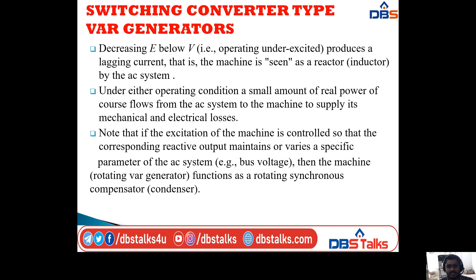If the excitation of the machine is controlled so that the corresponding reactive output maintains or varies a specific parameter of the AC system, such as bus voltage, then the machine functions as a rotating synchronous compensator, that is, a condenser.